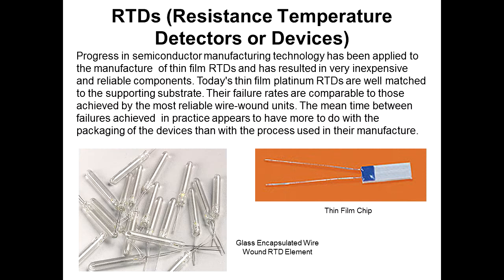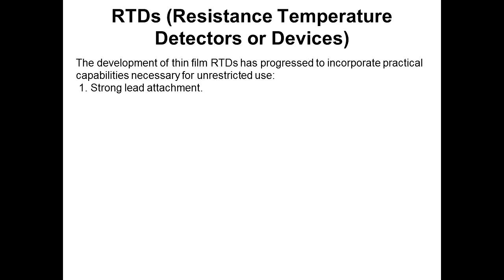The thin films are made to what's called a Heraeus method, where they're built in large volumes and computer laser trimmed. Then they're tested for accuracy. The ones that meet the Class B accuracy are sorted out, or Class A are sorted out as Class A's. The ones that fail Class A are checked for Class B. If they meet those standards, they're sorted out. If they do not meet that, then they go to Class C, and so on. And we'll get into what those mean in just a moment, the Class A, Class B, and Class C.